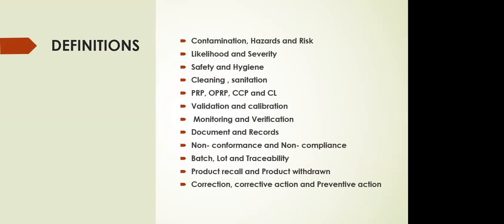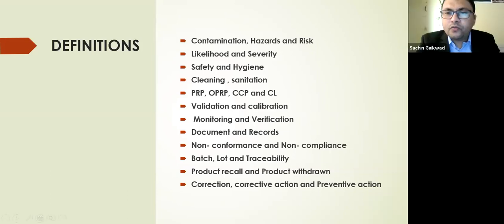So in a calibration, we are calculating what is the error in our instrument. Next time when you check the temperature of any material and you get 25.1 degrees Celsius, you have to correct that to 25 degrees Celsius, because the error in your instrument is 0.1 degrees Celsius. So that is your error. In a calibration, you are calculating the error which is traceable to the national standard. So once you know the error in the equipment, you can correct during the reading.